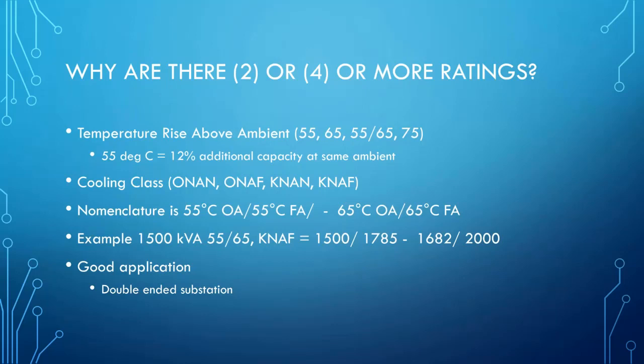in this slide. You could have your base rating, which is 1500 kVA. And the nomenclature of this is the slashes separate the fan rating from the non-fan rating, and the dashes separate the degree C rise ratings. Okay. So if you have a 1500 kVA transformer and you decide to specify 55 to 65 degree C rise, we call that a dual rating.